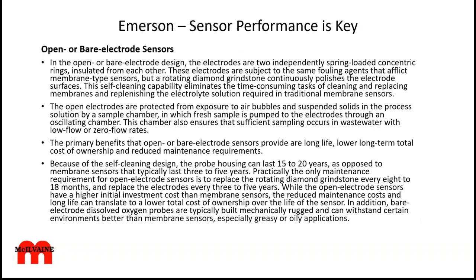It's essential to keep improving the sensors themselves. You're going to do no better with your system than the sensors. And if you've got a membrane DO sensor that is malfunctioning a good portion of the time, you've got a problem. But Emerson has a bare electrode design with a rotating diamond grindstone that continuously polishes the electrode surfaces. So you not only have lots of maintenance savings, but much more reliable sensing on a continuous basis.